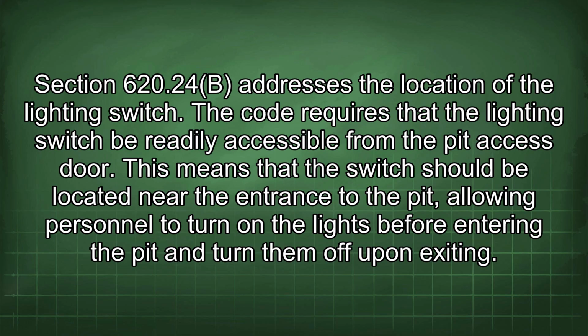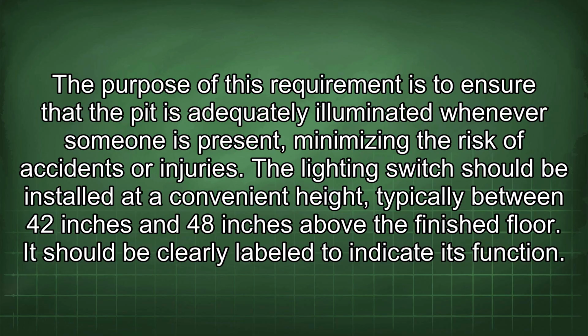Section 620.24b addresses the location of the lighting switch. The code requires that the lighting switch be readily accessible from the pit access door. This means that the switch should be located near the entrance to the pit, allowing personnel to turn on the lights before entering the pit and turn them off upon exiting. The purpose of this requirement is to ensure that the pit is adequately illuminated whenever someone is present, minimizing the risk of accidents or injuries.